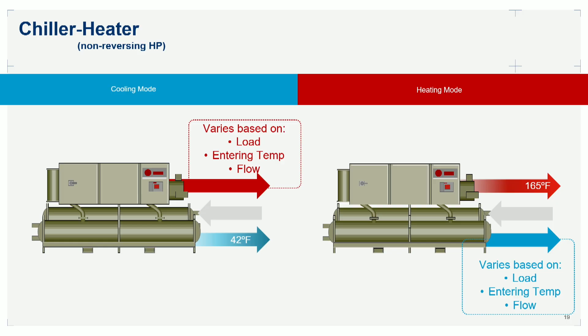What we tend to do in those cases is use a more traditional chiller that's used to making cold water, and making hot water in a condenser. We just do the switching on the hydronic side. So the machine itself functions just like a normal chiller, and is built pretty much exactly like one, but with a controls upgrade that lets us control to that hot water temperature. Then if we need any changeover, that's done on the hydronic side through valving.